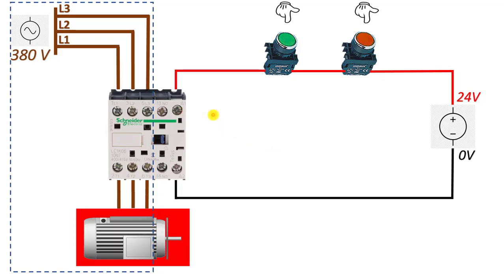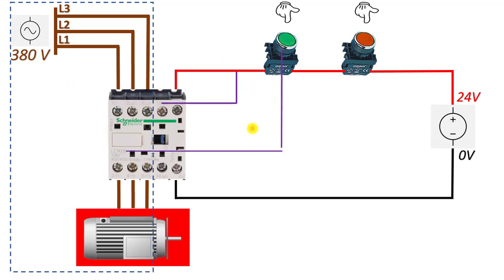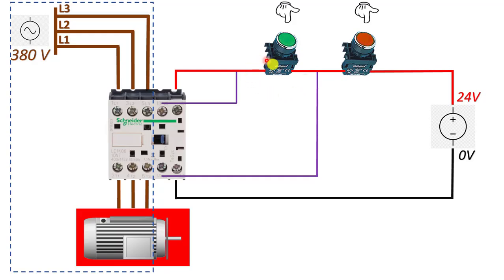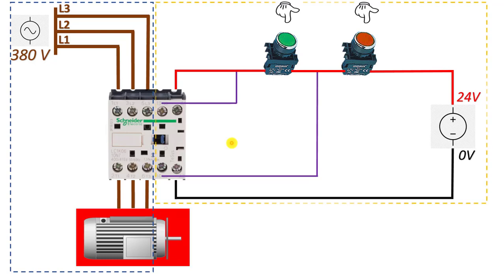When the required voltage is provided to the coil, the three main contacts and one auxiliary contact move to the closed position. For sealing, I use the auxiliary contact. I connect the input leg of the auxiliary contact to the start and connect its output leg in parallel with the start button. By connecting the auxiliary contact in parallel with the start button, even if I release the start button, the circuit continues to be completed through this auxiliary contact and the system keeps running.